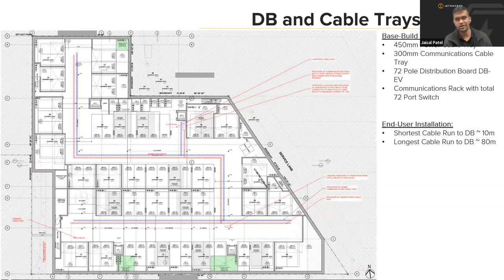So the EV chargers are not installed as part of a day one install. The cable trays, distribution boards, and comms racks are all run day one during the base build installation. And then as a tenant buys an electric vehicle, they'll get a charger installed and run it back to a centralized distribution board. So we have a 450 mil power cable tray that's sized for 68 circuits running throughout the car park to the distribution board for EV charging.